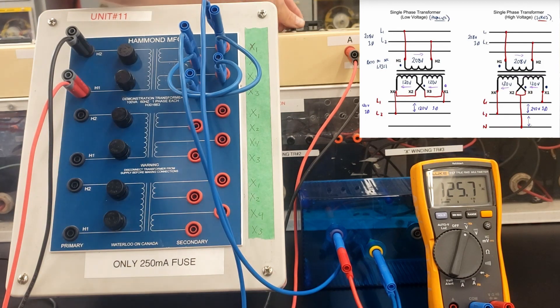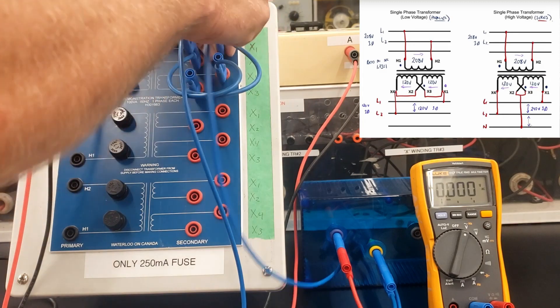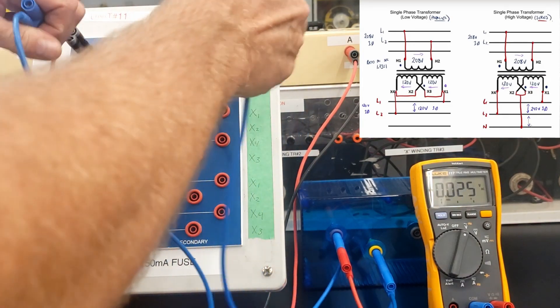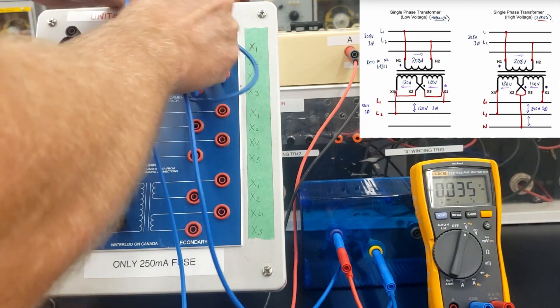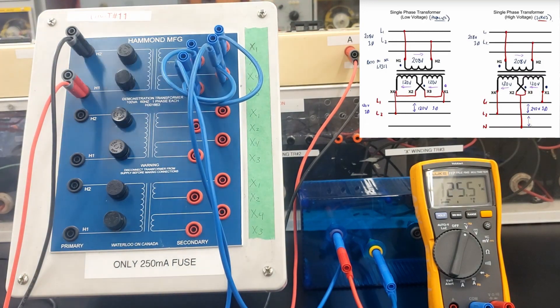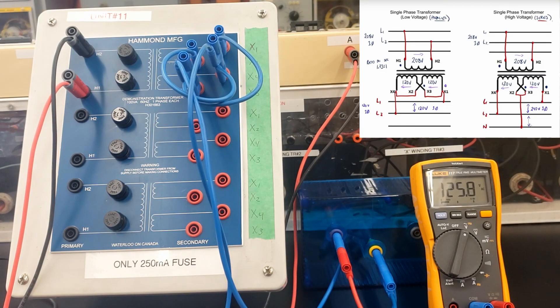I have 125 volts between X1 and X2. And I have 125 volts between X3 and X4. If I wanted to test out the voltage between X3 and X4, then I move these guys down to X3 and X4. Energize the circuit again. And I got 125 volts on that winding as well.